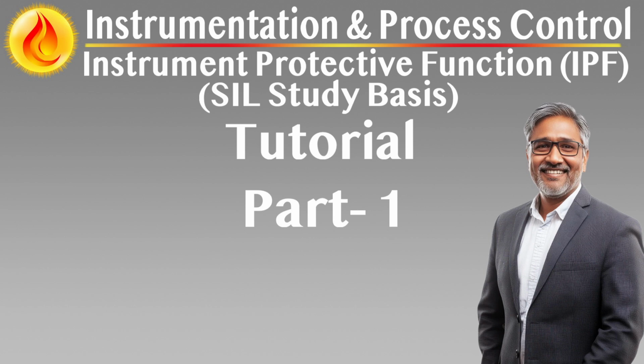Integration with process hazards and alarm management. IPF design must be tightly integrated with process hazard analysis, e.g. HAZOP, LOPA, to ensure that the function responds to the correct hazard scenario. Where possible, IPFs should not overlap with high-level alarms or interlocks unless explicitly coordinated through the safety design strategy. Each IPF must be clearly mapped to its cause and effect logic, with time-stamped event logs available for troubleshooting and audit purposes. The alarm system must be configured to differentiate between IPF activation, process alarms, and equipment faults.